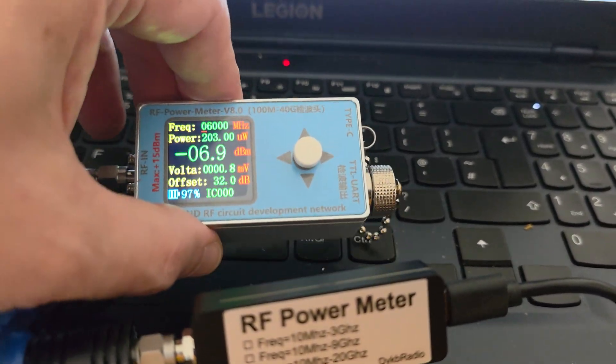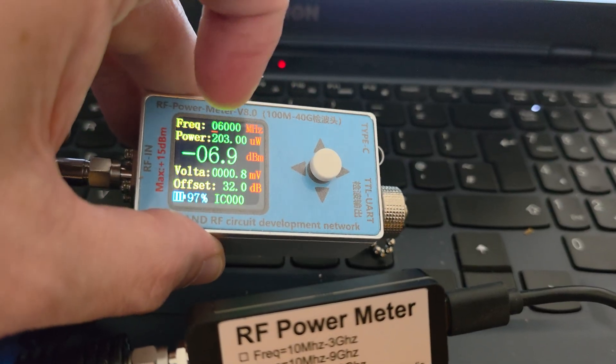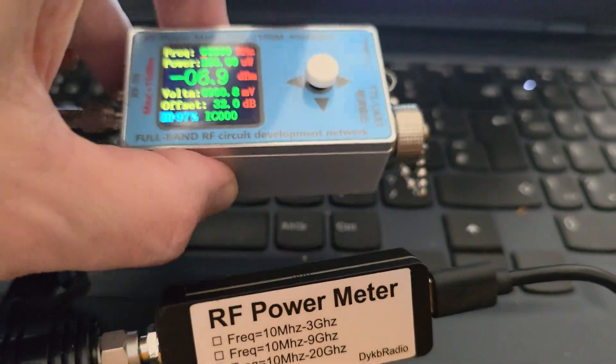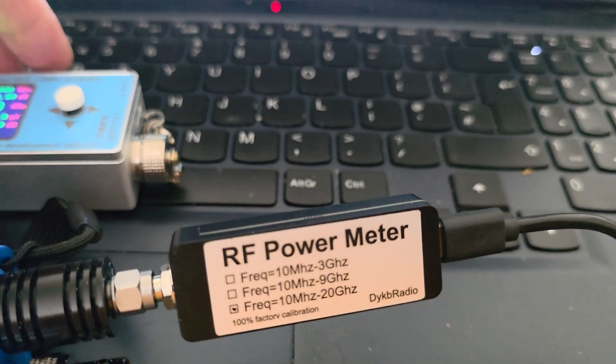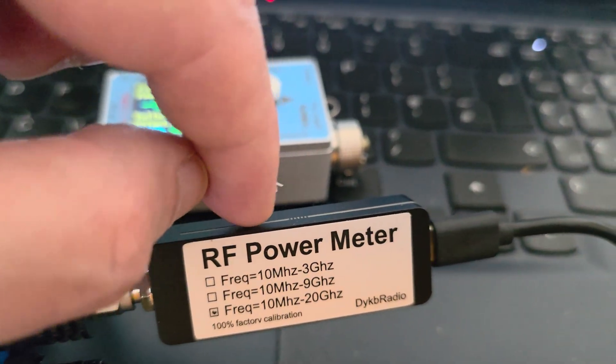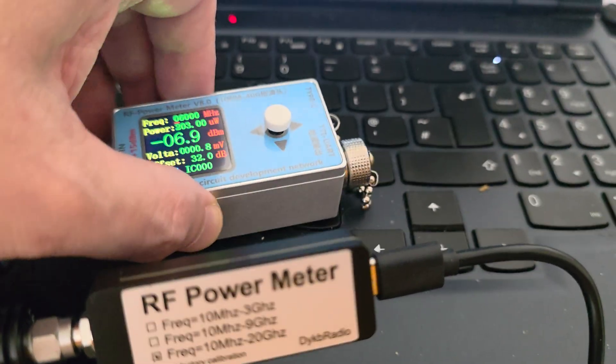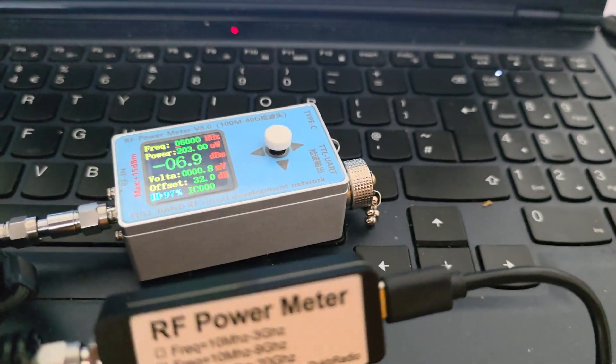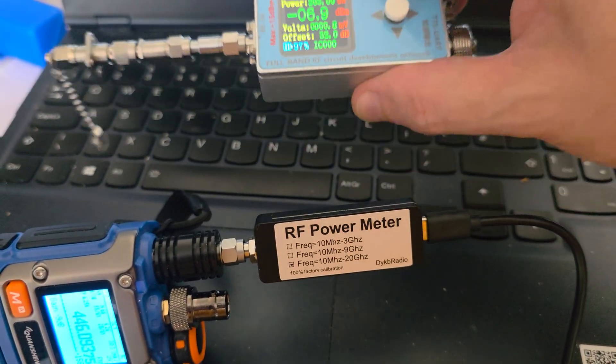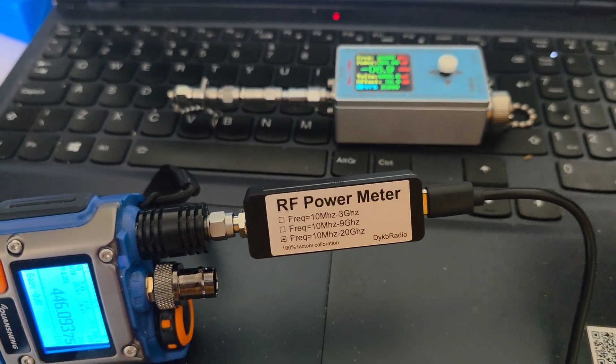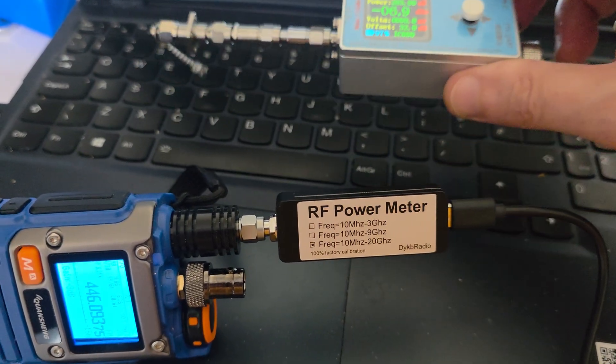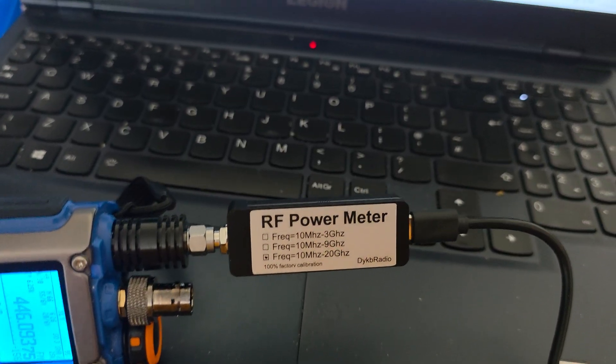At higher frequencies, this calibration is better than this one. But up to 6 gigahertz, this one has a deviation of two decibels that is known and always corrected there. So the calibration of this one in some ranges is better than this one, which is better than this one. But obviously this one's screen is better, and at the highest frequencies this one works better.